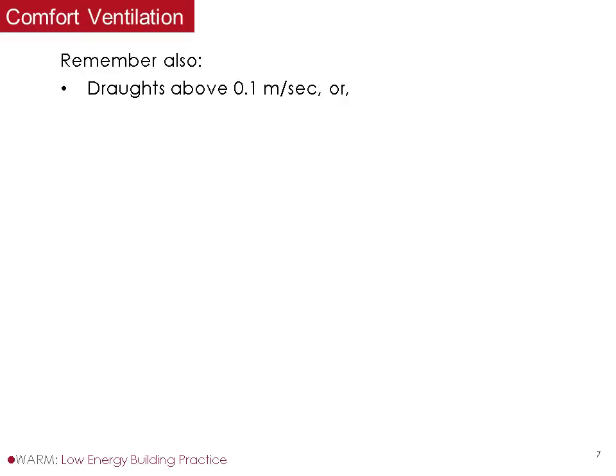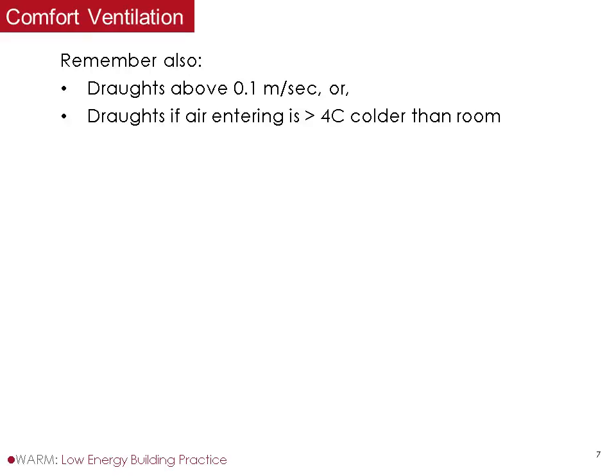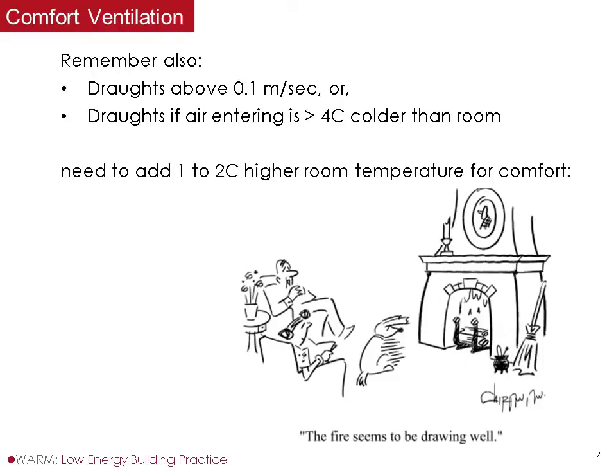The important things about comfort and ventilation are drafts. If you get air moving more than 0.1 metre per second, which isn't very fast, or air entering more than about 4 degrees centigrade colder than the room temperature, you'll get a downdraft. As soon as that touches you anywhere on the back of the neck, the waist, or the ankles, if those are bare, you'll need 1 to 2 degrees C higher room temperature to get the same level of comfort.